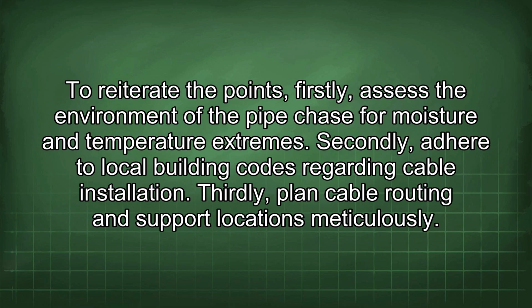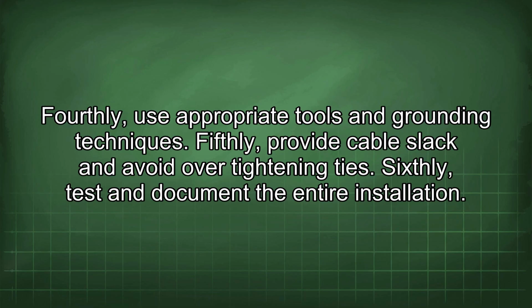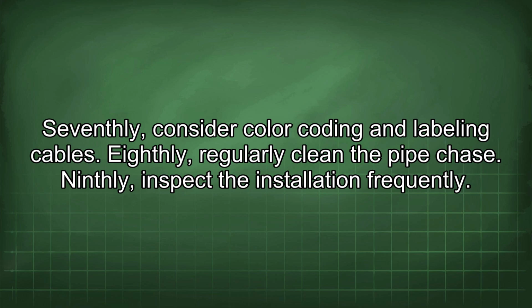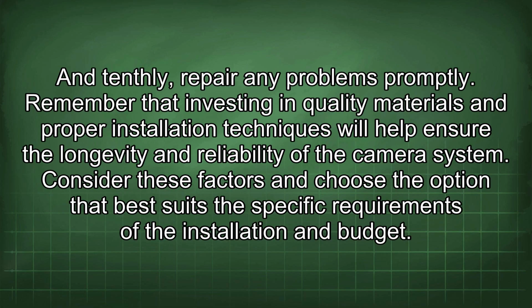To reiterate the points, firstly, assess the environment of the pipe chase for moisture and temperature extremes. Secondly, adhere to local building codes regarding cable installation. Thirdly, plan cable routing and support locations meticulously. Fourthly, use appropriate tools and grounding techniques. Fifthly, provide cable slack and avoid over-tightening ties. Sixthly, test and document the entire installation. Seventhly, consider color coding and labeling cables. Eighthly, regularly clean the pipe chase. Ninthly, inspect the installation frequently. And tenthly, repair any problems promptly.